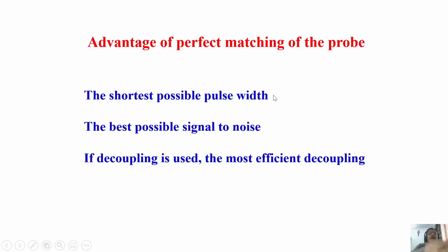Another advantage is that you have a uniform excitation over a wide spectral bandwidth. That's what I said when I was explaining the RF pulse. For a uniform excitation of a wide bandwidth, you need a short pulse width. That's very good, and that is possible with a perfect matching. So when you have a perfect 90-degree pulse, perfect excitation, your signal to noise ratio will go up. You get the full signal you are going to detect.